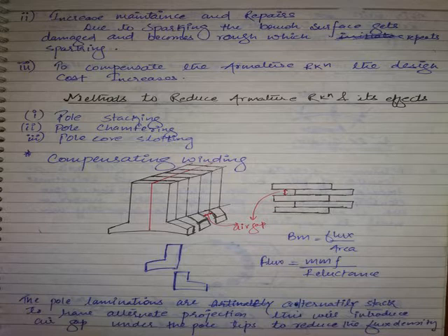Here you are introducing the reluctance by stacking alternate projections under the pole. Here the pole is normal only, pole stacking is not there, but the diameter of the pole core circumference is more than that of the armature. By designing properly like this, you can maintain minimum reluctance at the center of the pole and increase the reluctance towards the pole tips. This will automatically reduce the flux density as well as iron loss. But again, what is the concept? The net reluctance in the machine will increase. It demands more MMF. Same concept.